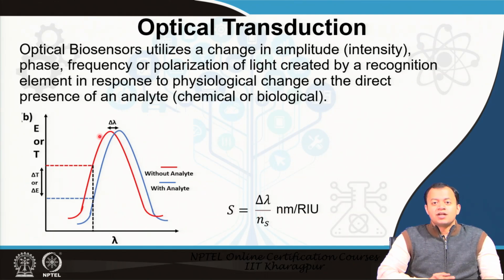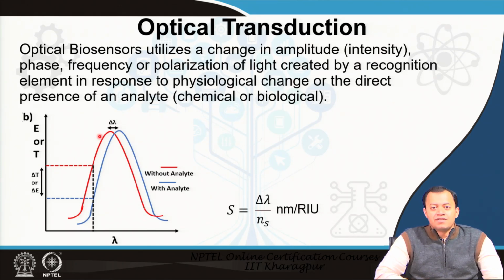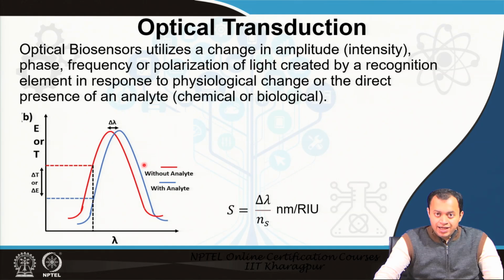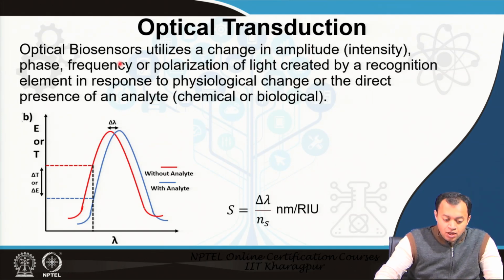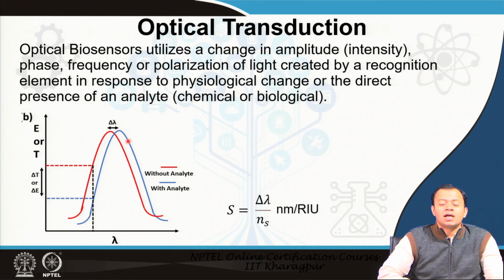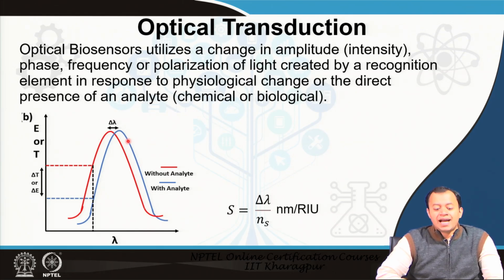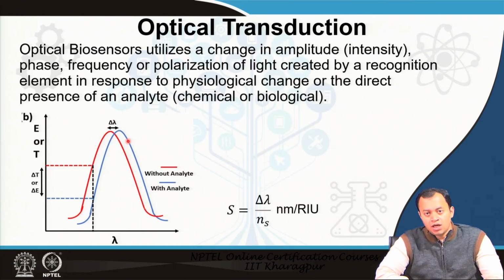So, understand this: transducers, optically, electromagnetically active surfaces, have some sort of an optical response, a particular signal, with a specific frequency, specific phase or polarization and a specific amplitude when excited by a light. Now, you put some amount of biological material, analyte, on top of that same transducer. The optical property, the amplitude, phase, frequency will undergo a modification. We quantify the modification and thereby we back calculate what are the properties of the coating, what are the properties of the analyte that has been put on top of your transducer. It is as simple as that.